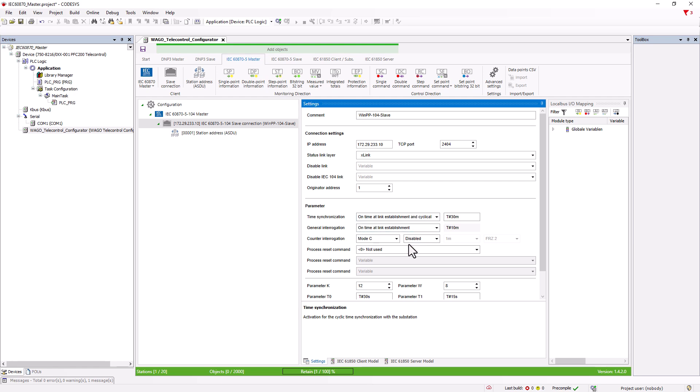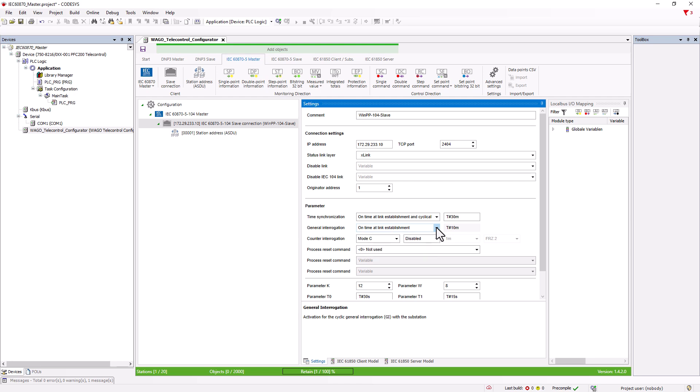In most cases, the master will trigger a general interrogation when the connection is established in order to have an up-to-date process image. During operation, the spontaneously or cyclically sent telegrams follow so that the master always has the current status, as long as the link is active.